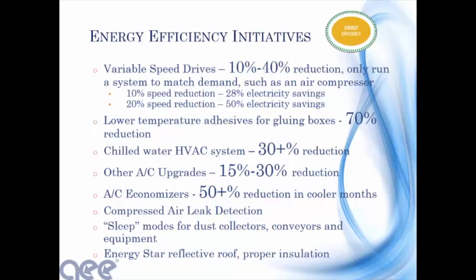We didn't necessarily justify a brand new air conditioning unit with a 3-year payback. But they had to be replaced, and it was not hard to justify the incremental cost of getting a more efficient unit over a standard model. Some other air conditioning upgrades that weren't chilled water, you could still pick up 15 or 20%, getting the higher SEER ratings if it was like a heat pump on a small office. So we do specify above and beyond the minimum standards for heat pumps.